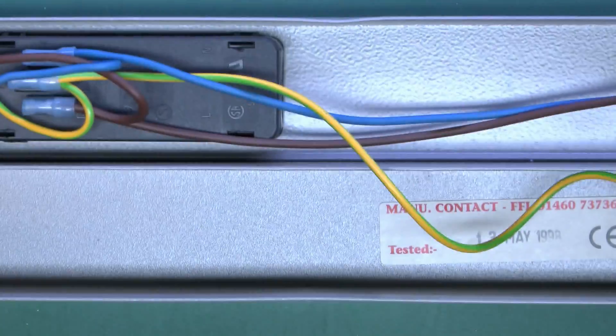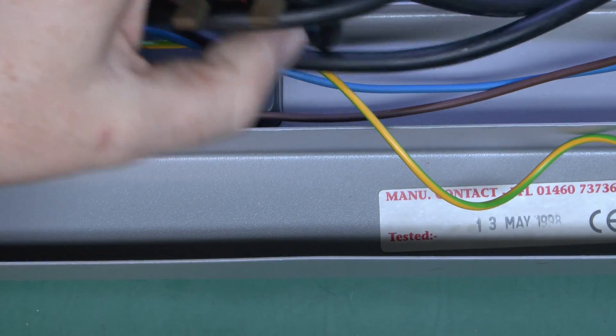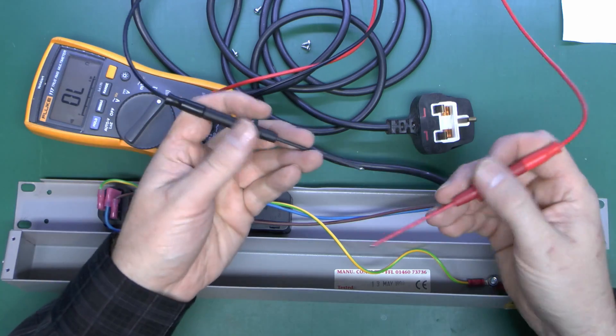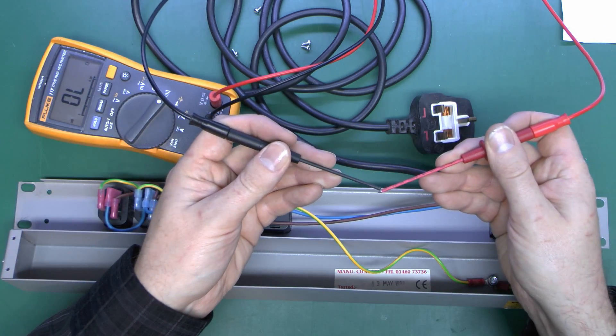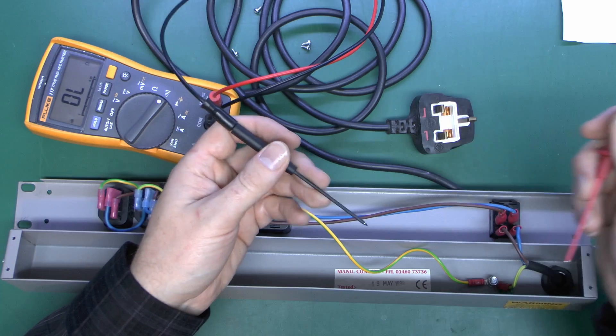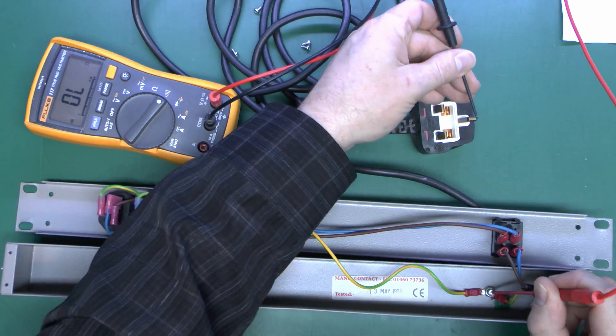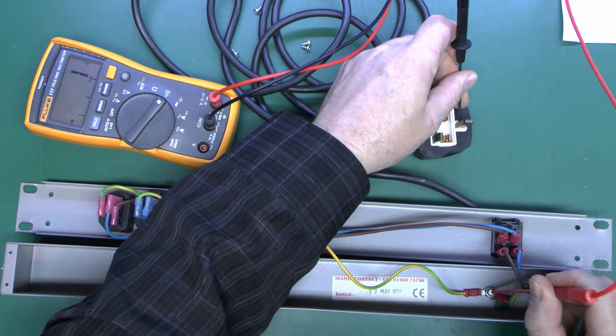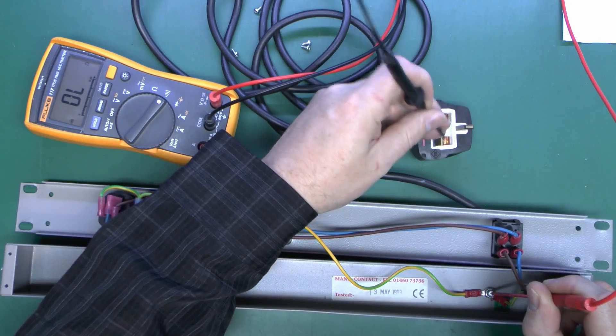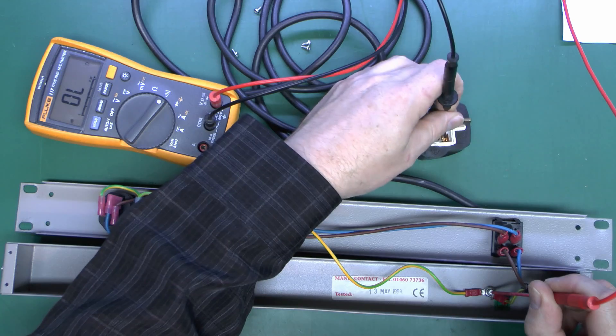So let's just see if this mains lead is actually damaged or defective in any way. I've just got this set to continuity, so just press those together and of course that will beep there. So we should have Earth connected to here from the pin of the plug, which we have. And there should be nothing connected to any of those, obviously.